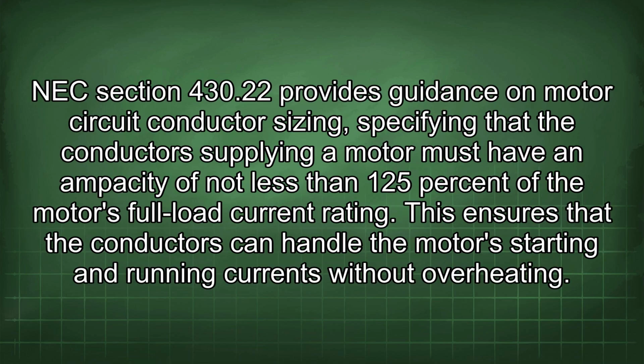NEC Section 430.22 provides guidance on motor circuit conductor sizing, specifying that the conductors supplying a motor must have an ampacity of not less than 125% of the motor's full load current rating. This ensures that the conductors can handle the motor's starting and running currents without overheating.